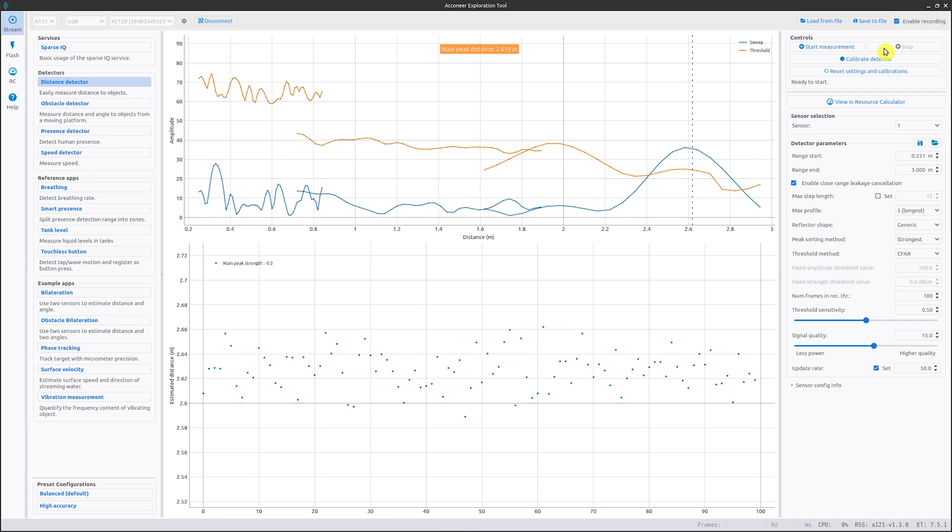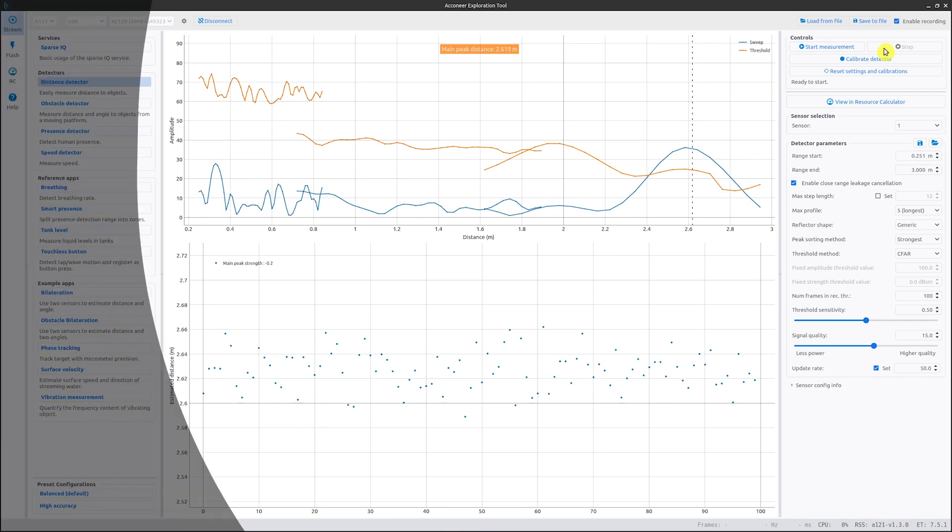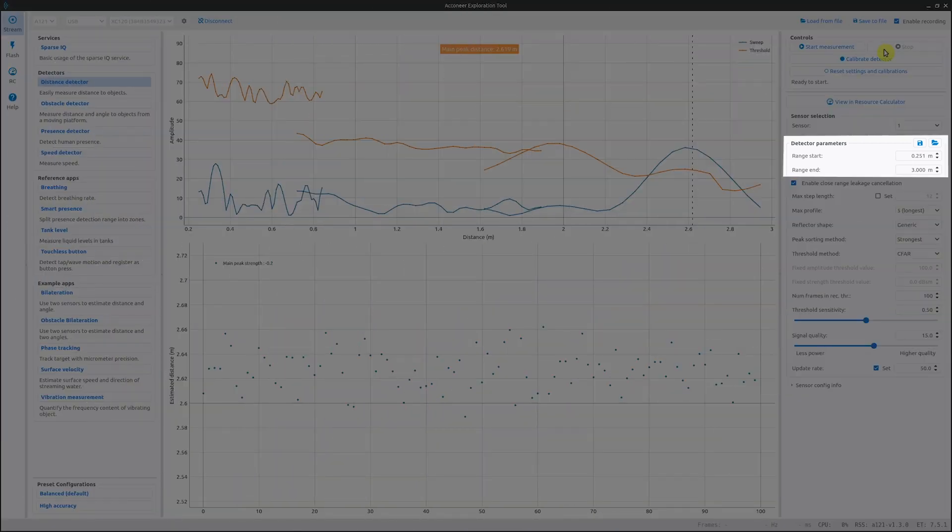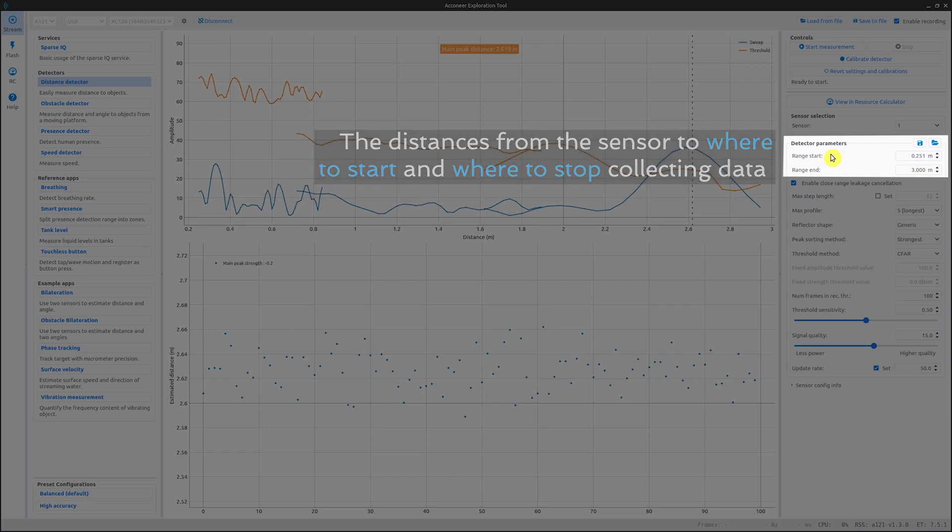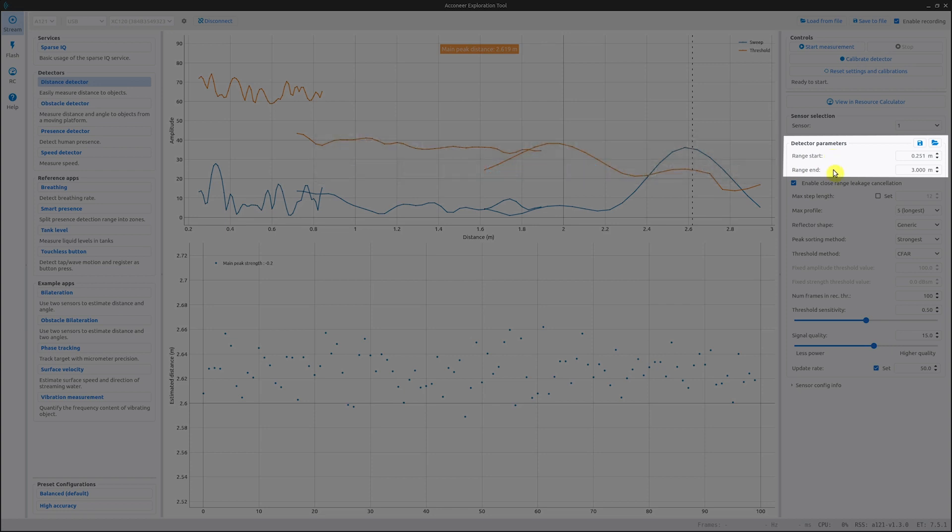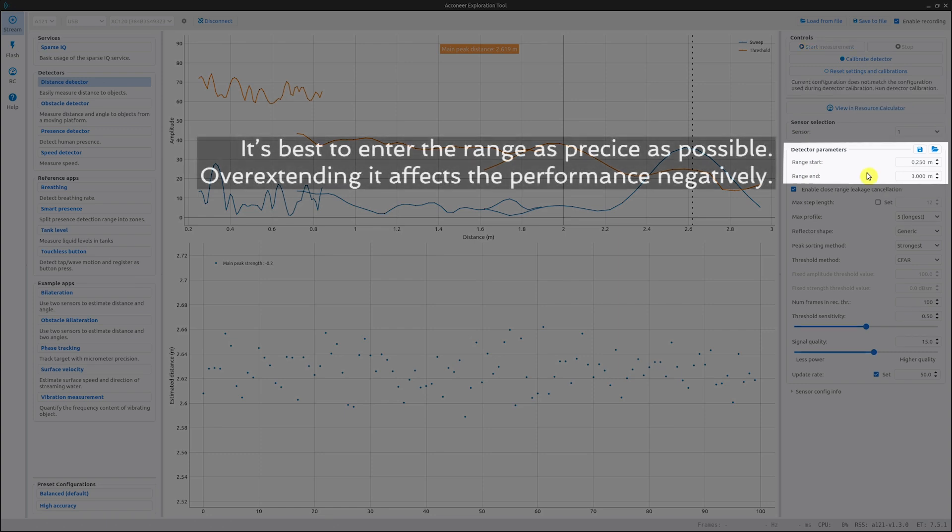Now let's go through the detector parameters. The first ones are range start and end. These set the start point and end point of the measurement interval in meters. Remember not to set range end further away than the actual distance you want to measure, since this results in higher power consumption and can result in unwanted effects.